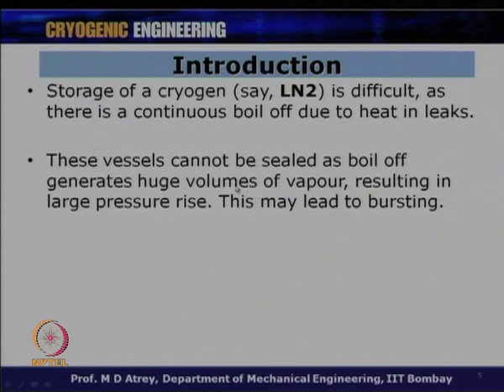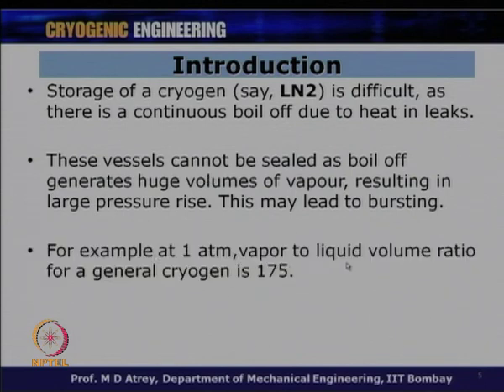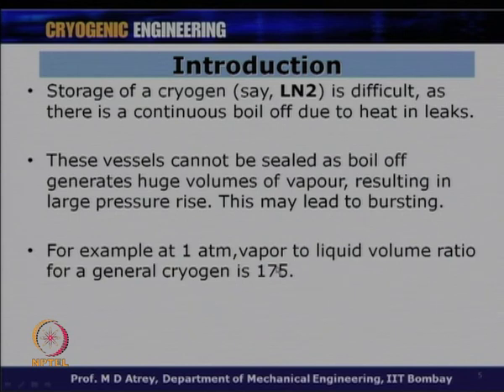We want to reduce this boil-off; we cannot keep cryostats or cryo-containers completely closed with sealed lids. The boil-off will always occur because heat in-leaks will always occur, though we can minimize them. At one atmosphere, the vapor-to-liquid volume ratio is of the order of 175 — one liter of liquid produces around 175 liters of vapor. If there is insufficient volume available, pressure will start increasing in the cryostat, which can be dangerous. We have to allow boil-off to come out while minimizing it so experiments can last longer.